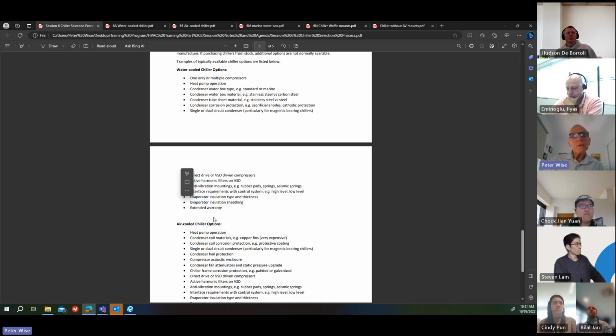We've got evaporator insulation and thickness. So various options here. The evaporator has to be insulated. So the manufacturer, as a standard, will put on the insulation to achieve the MEPS ratings or the NCC requirements. And that might be 25, probably more like 40 mil thick insulation. But you can get thicker if you want that. So you can get 50 mil. You can probably get 75, but normally you might go to 50 mil.